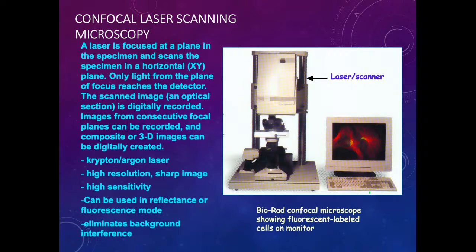Now, confocal laser scanning microscope. Let's focus on this. In this we use laser light actually. A laser light is produced on a plane of XY axis. That is like a normal microscope. From the top, the laser scanner is there.